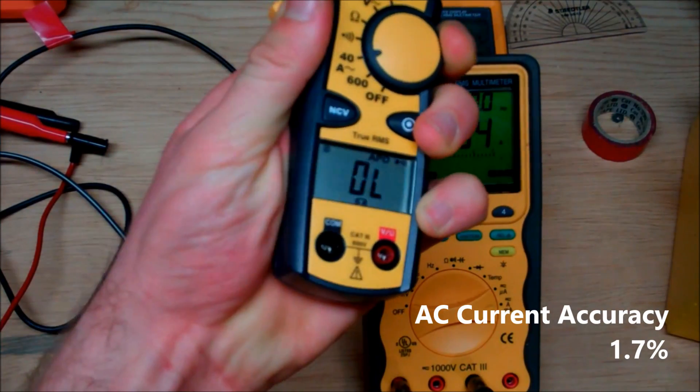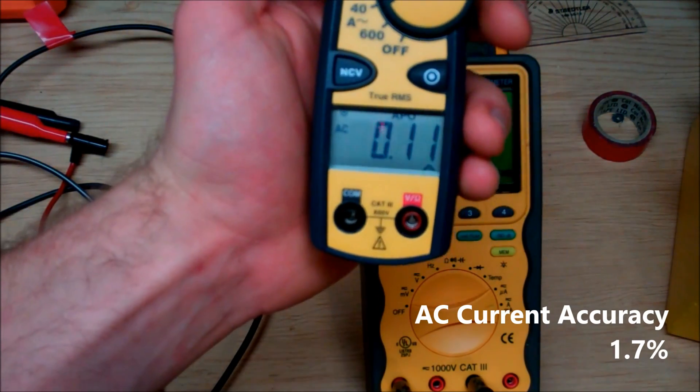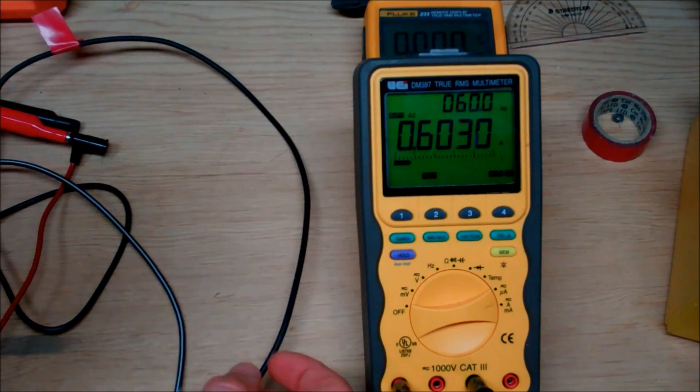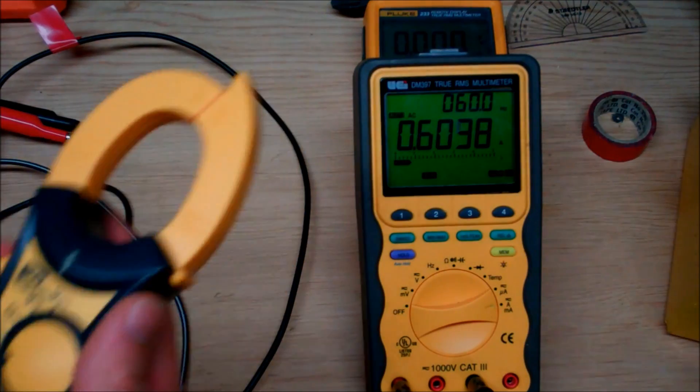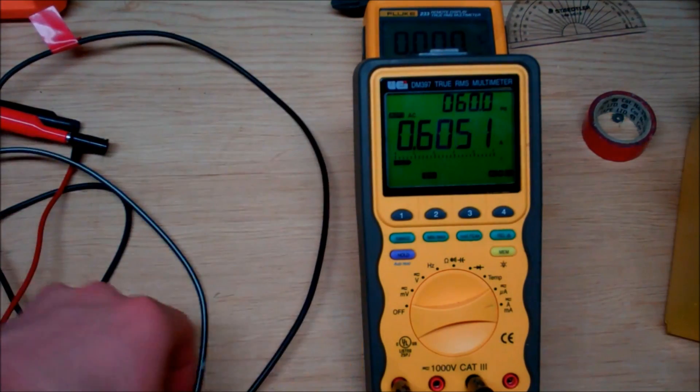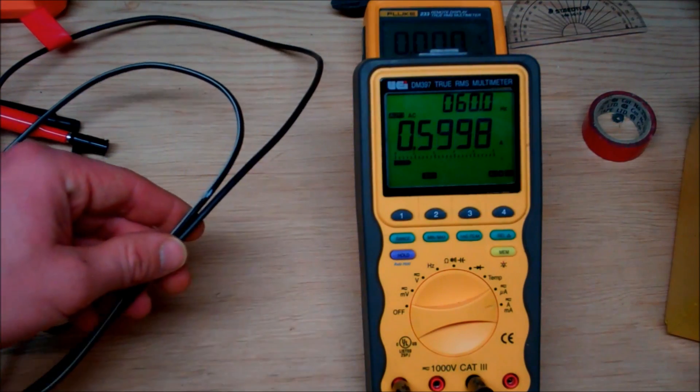Now as we scroll to our next function, we have the ability to measure current for a range of 40 amps and 600 amps. What I have here is an isolated power supply line going to my AC to DC converter from my laptop. Once again, this is isolated because if you measure both, you won't establish a reading because you have two currents and they cancel each other out.